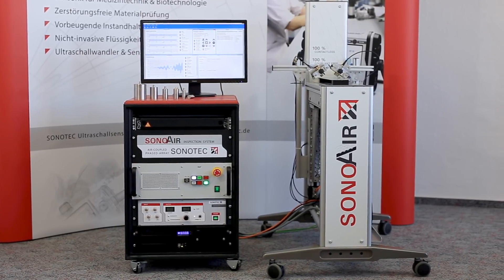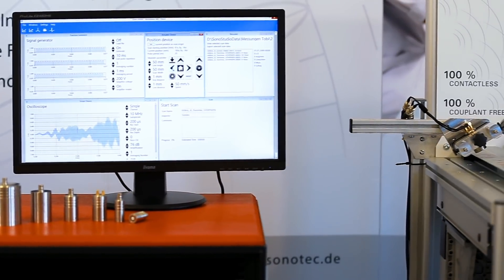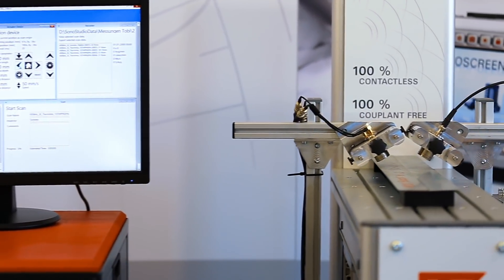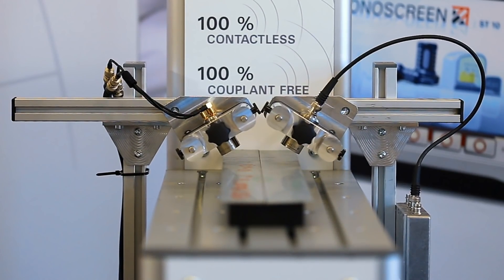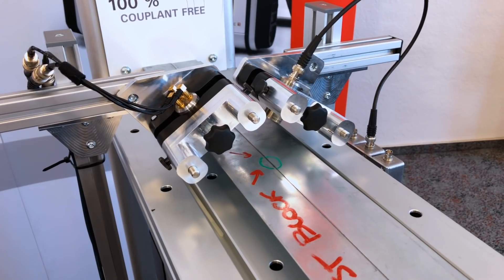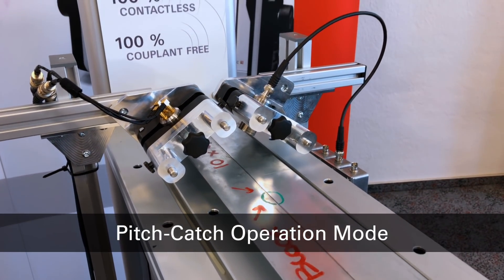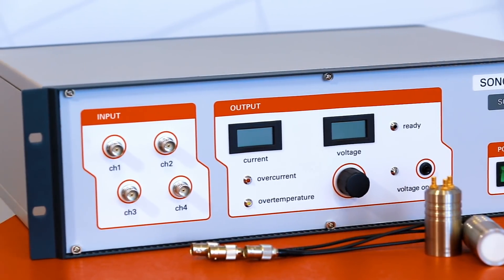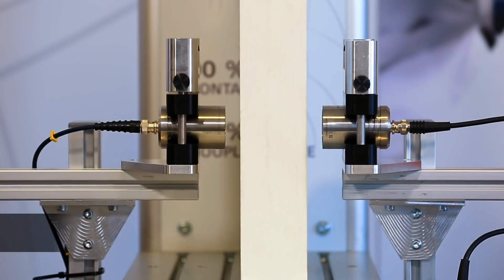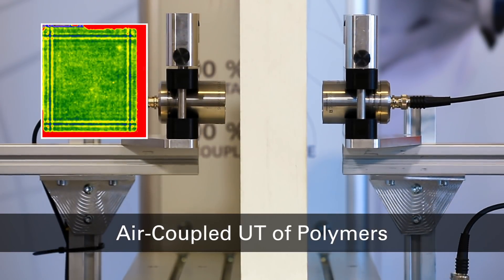We from Sonotec have recently developed the Phased Array Air Coupled Ultrasonic Inspection System SonoAir for contact-free non-destructive testing. The SonoAir features an innovative pitch-catch operation mode for one-sided inspection of thin metal weldings, composite laminates and other structures. The standard inspection mode for air coupled ultrasonic testing is through transmission.